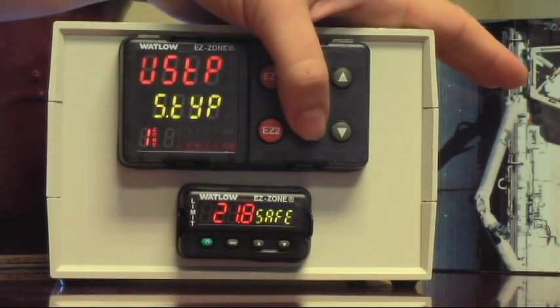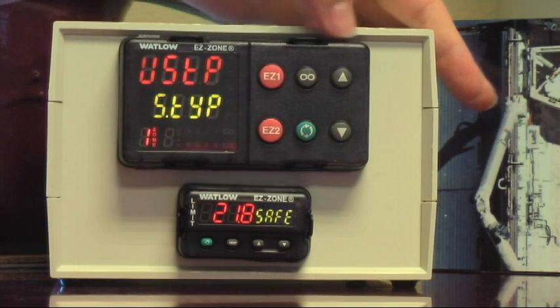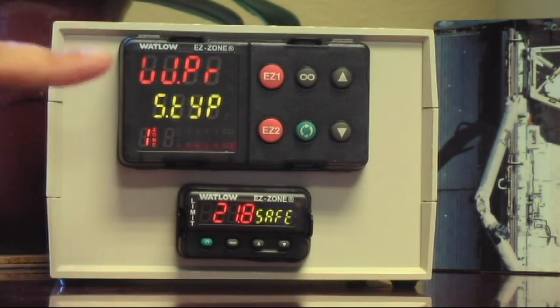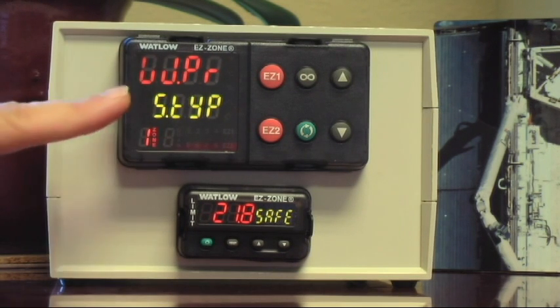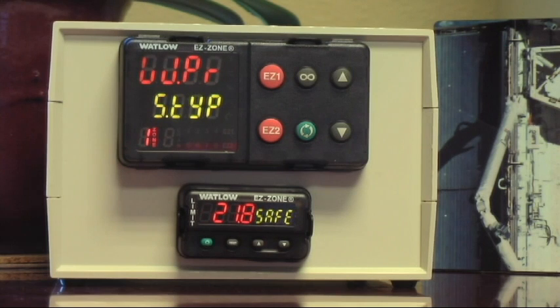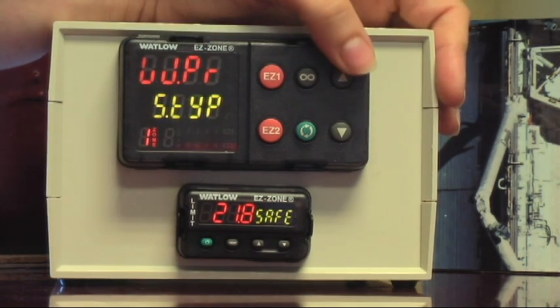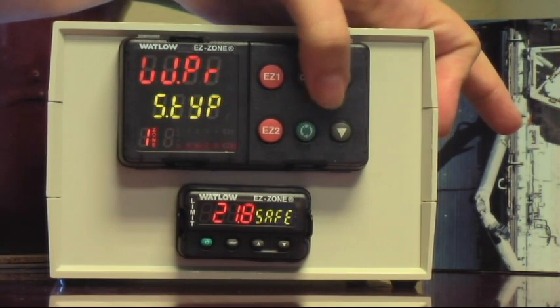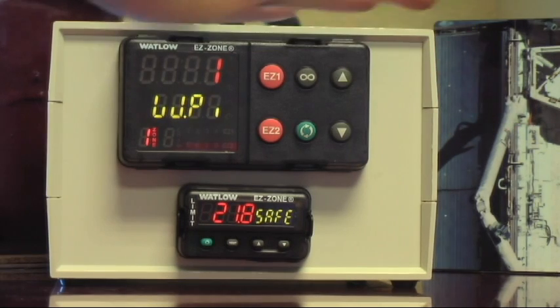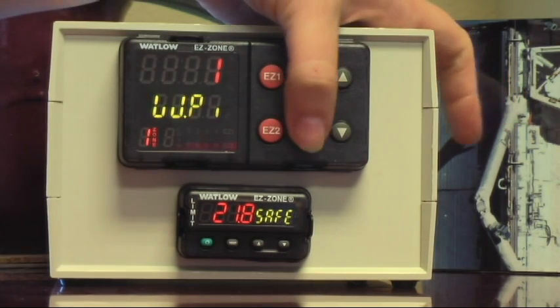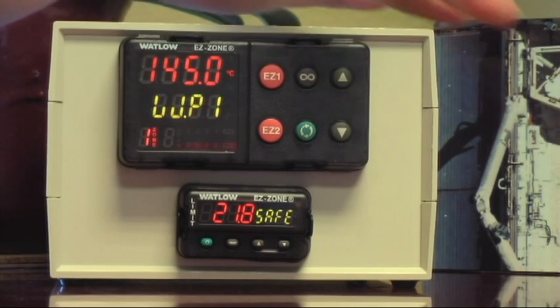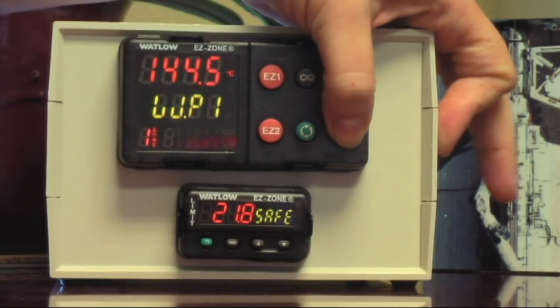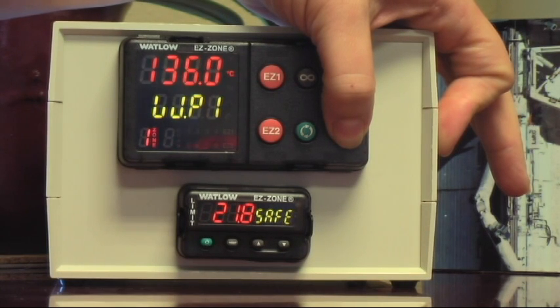Green key. This step is going to be a wait for process. So we're going to select wait for process. That's the step type. Now what that means is wait for this next thing to happen before you start the timer. And the thing that we want to happen is we want to get close to our set point. Green key. So we're going to wait for process one. That's right. And we're going to say, since your set point is a hundred, we're going to say before you start the timer, wait for about 95 degrees.